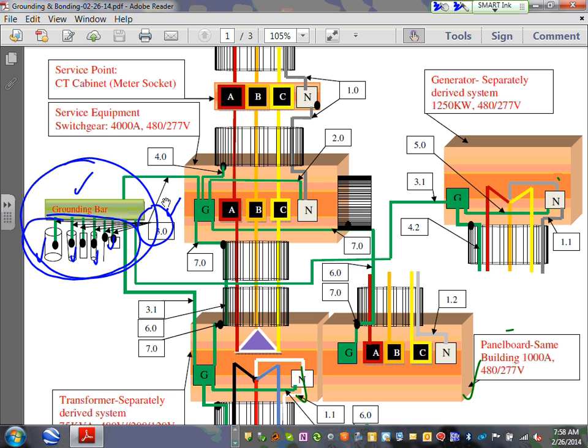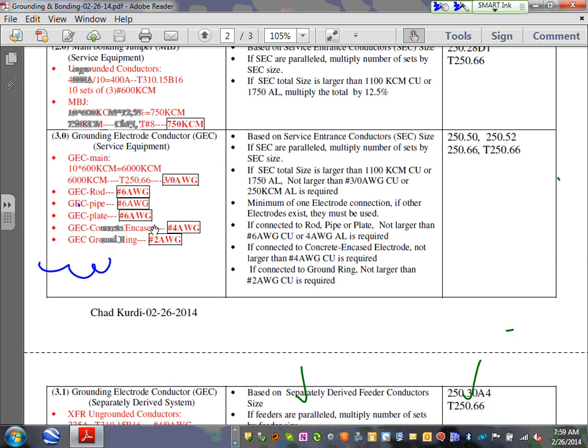When we went to Boston Scientific, did you guys see the 500 kcmil big, thick conductor ground ring? They call it a ground ring, tied to the ground ring. This is what's going to ground and bond your system to Mother Earth. Can I just get you to understand that 3.0 is the conductor, and for each one of these guys, first you bring one into the ground bar, and then from the ground bar, Adam, you go to each and every one of these grounding electrode systems. These are grounding electrode systems. Okay, so let's go look at 3.0, shall we? 3.0, gentlemen, right here. I would like you guys to look at 3.0.